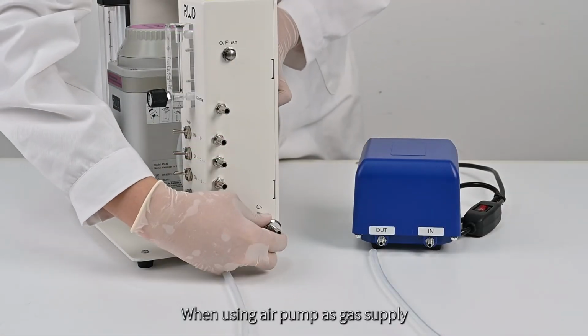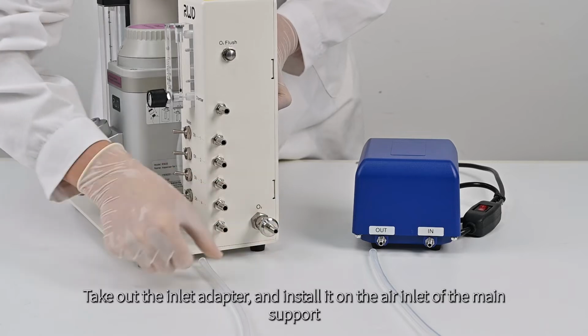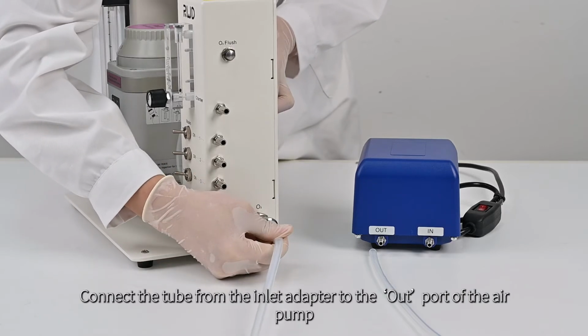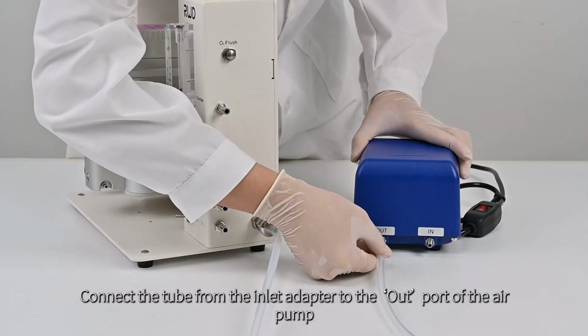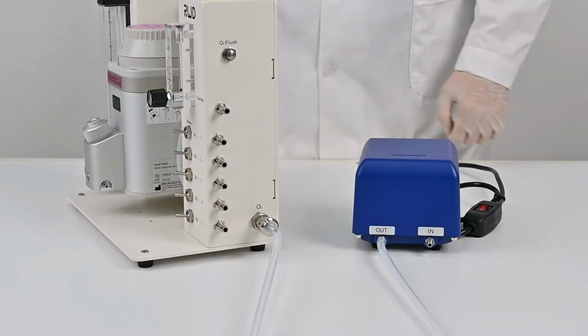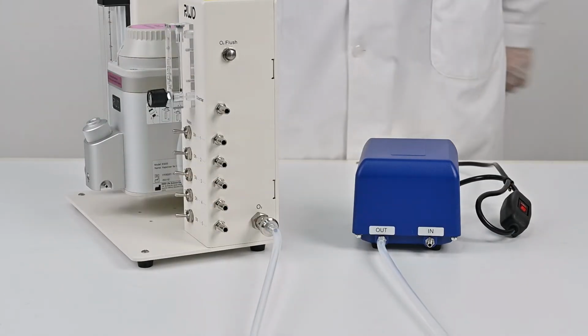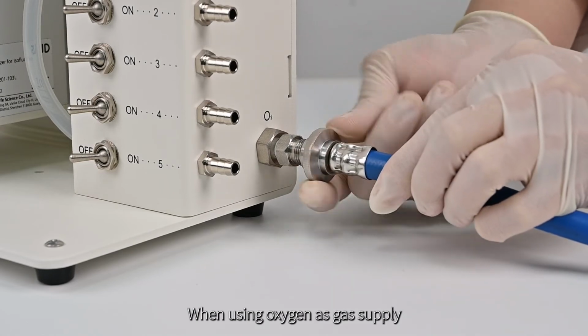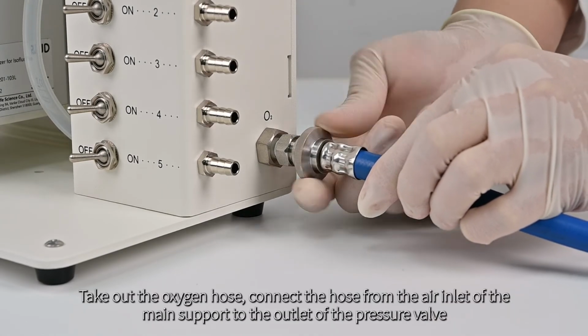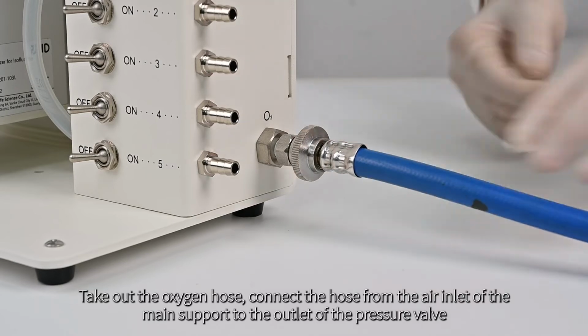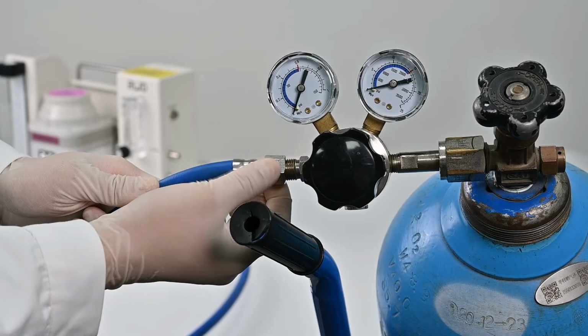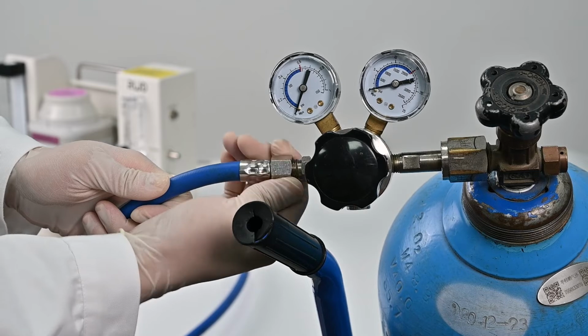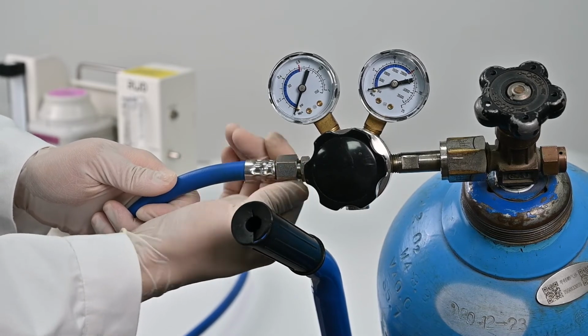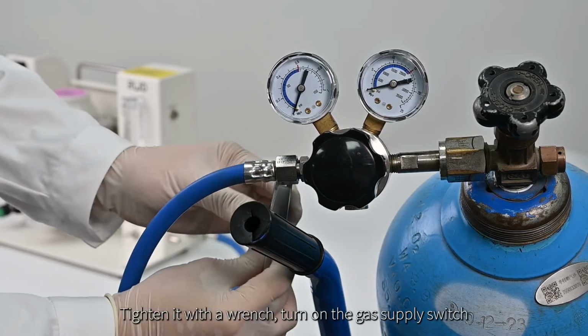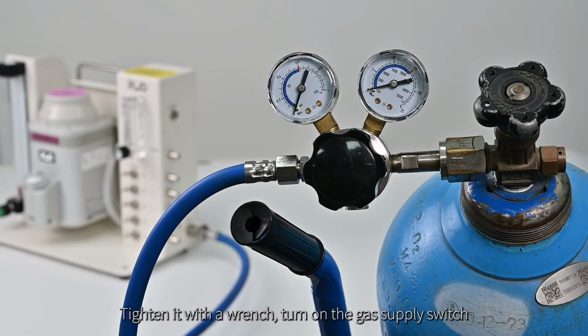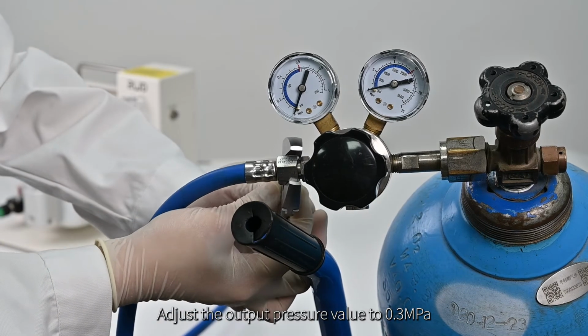When using air pump as gas supply, take out the inlet adapter, and install it on the air inlet of the main support. Connect the tube from the inlet adapter to the output of the air pump. When using oxygen as gas supply, take out the oxygen hose, connect the hose from the air inlet of the main support to the outlet of the pressure valve. Tighten it with a wrench, turn on the gas supply switch, adjust the output pressure value to 0.3 megapascal.